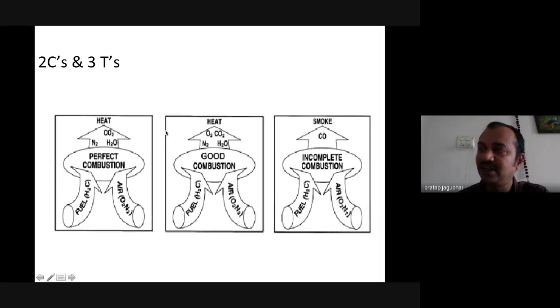To give more detail on how to control this stack loss, we need to go slightly deeper into the combustion side. Combustion is basically chasing complete combustion. That's why 2C. Ideally we should have combustion without O2, but it is very tricky and very unsafe. We should have slightly excess air available for better combustion. If we don't give sufficient oxygen, there will be black smoke. This CO will take away heat from the furnace, and heat is getting lost out to the atmosphere, which is again a loss.